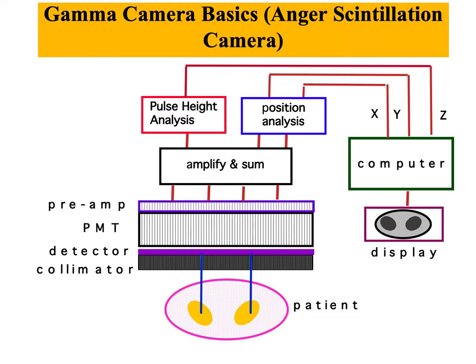You can see the scintillation crystal here in the image — it's this part here. Then we will talk about the collimator. This pink rectangle is the detector, and this is the collimator that we're going to describe shortly. Then we have the photomultiplier tubes in this rectangle, followed by the pre-amplifier, amplifier, pulse height analyzer, position analyzer, and then the computer to process the data and display your nuclear medicine image.